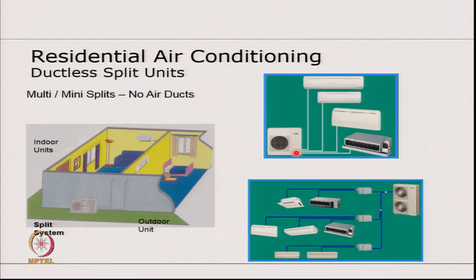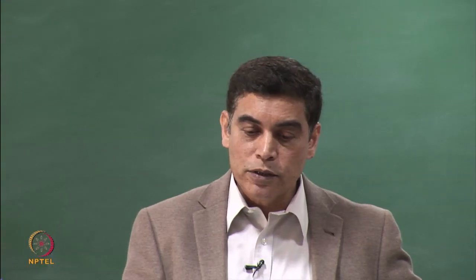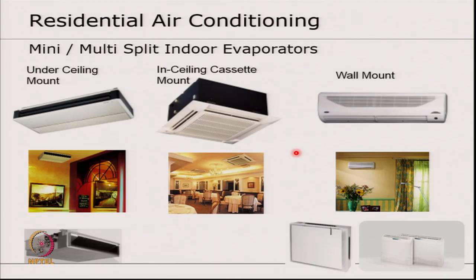The key feature of ductless split units is the very name. You don't need a duct to spread air in the conditioned space, and for that reason they are simpler to install, maintain, and service. Then these are some other types of units for which we will end up having evaporators designed. These are becoming less and less popular, but if it is a large room you could consider a unit of this nature. Then we have in-ceiling cassette units, and these are the ones where I was mentioning the need for a condensate pump. If you need to have it in the ceiling, the design is such that you need a pump to ensure condensate is thrown out. Wall mount, I'm sure all of us have seen and are familiar with.